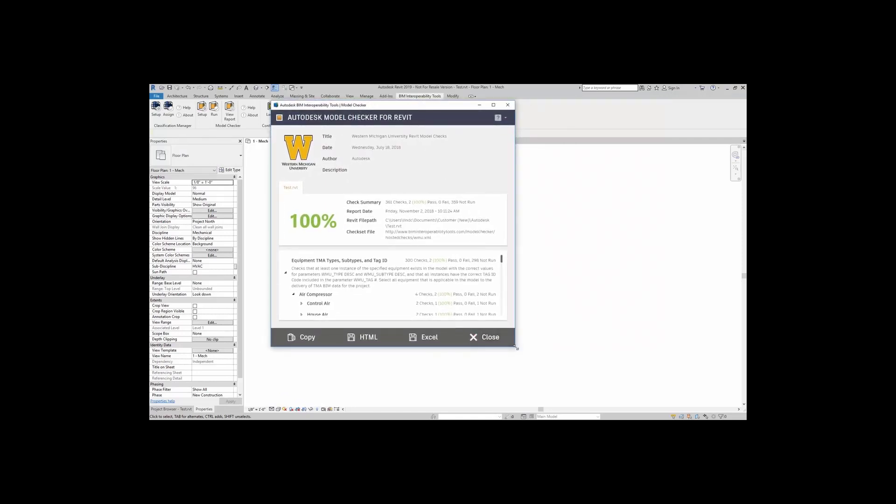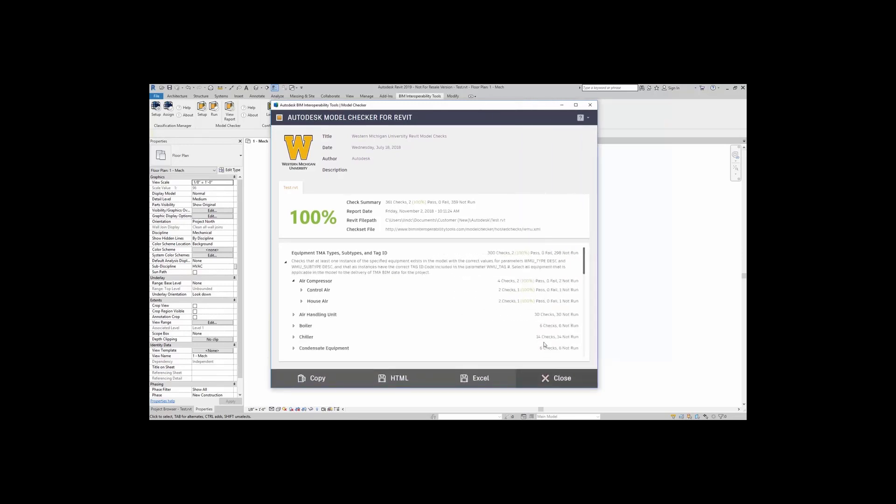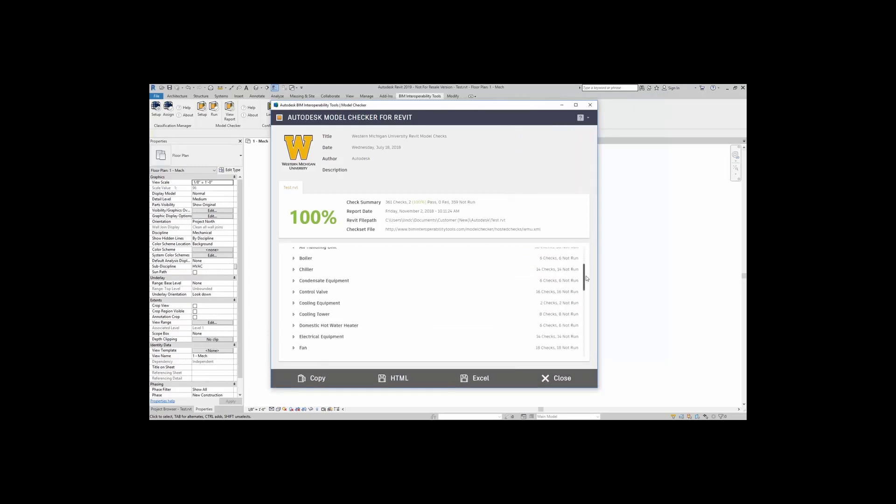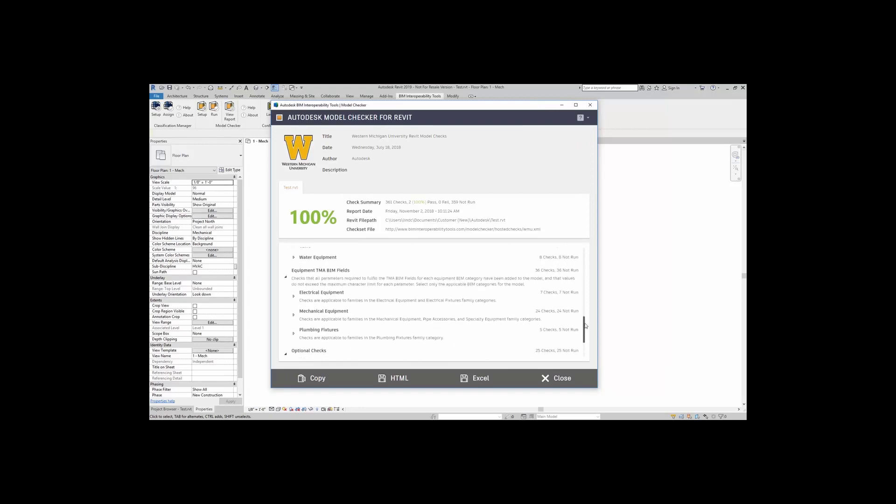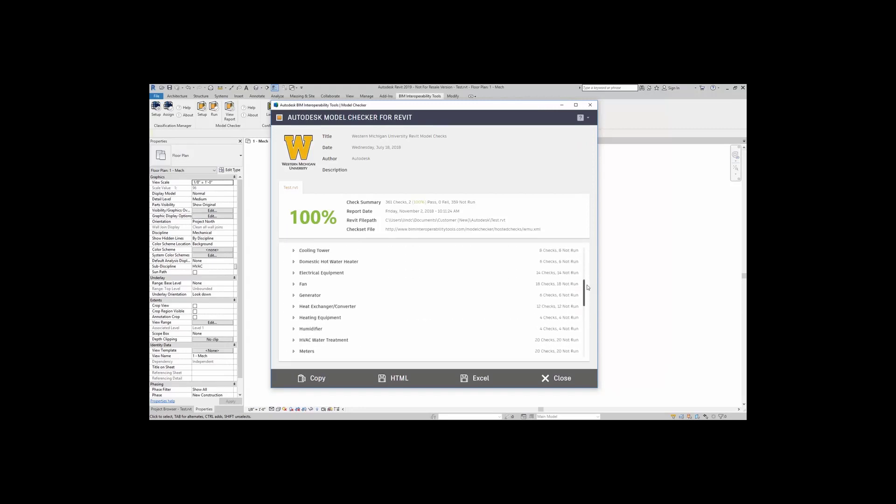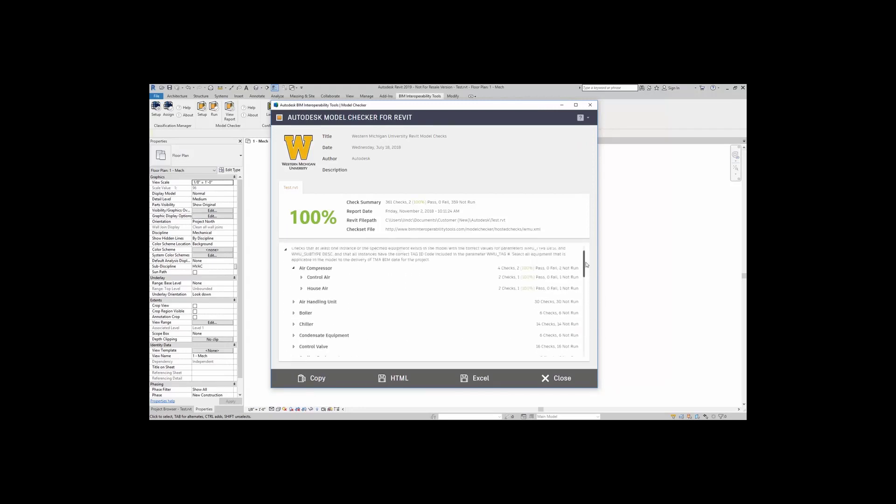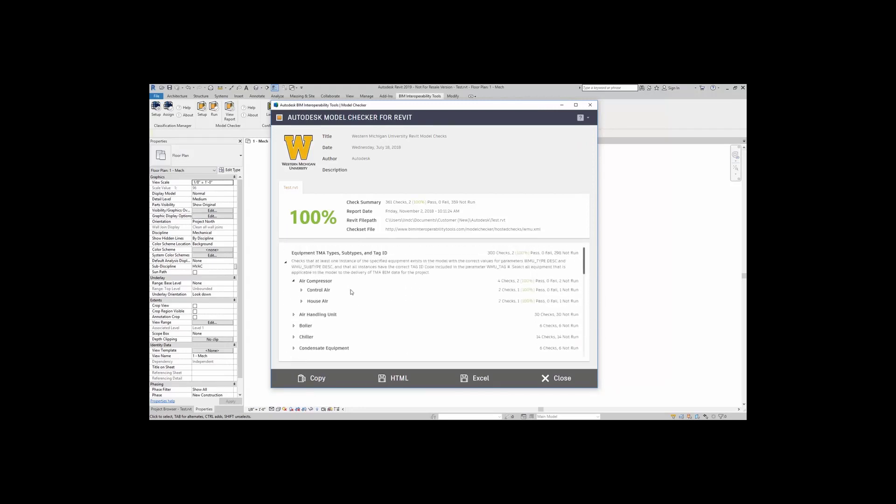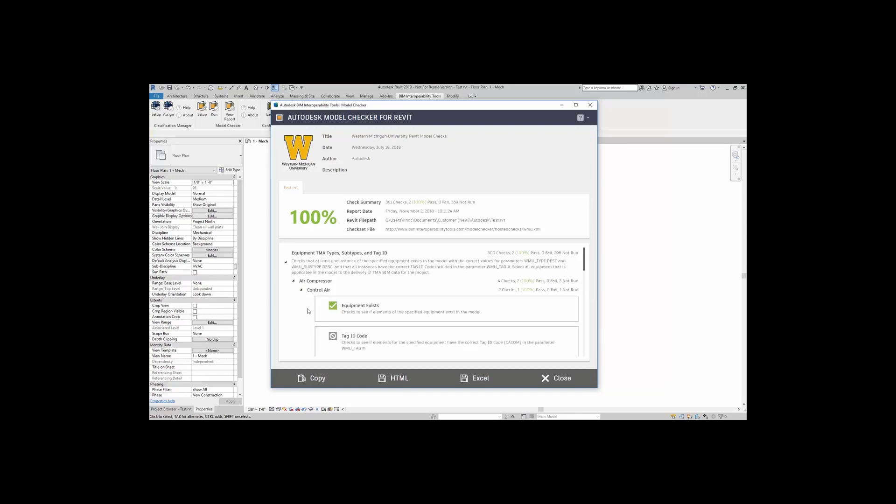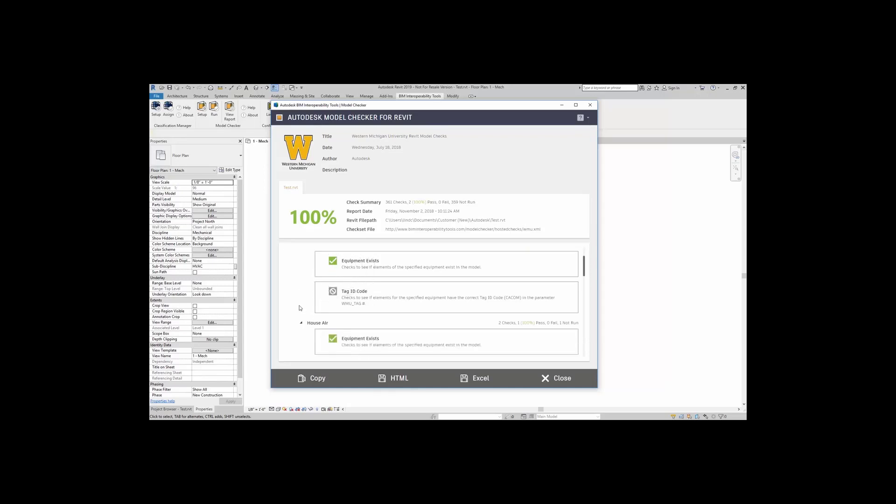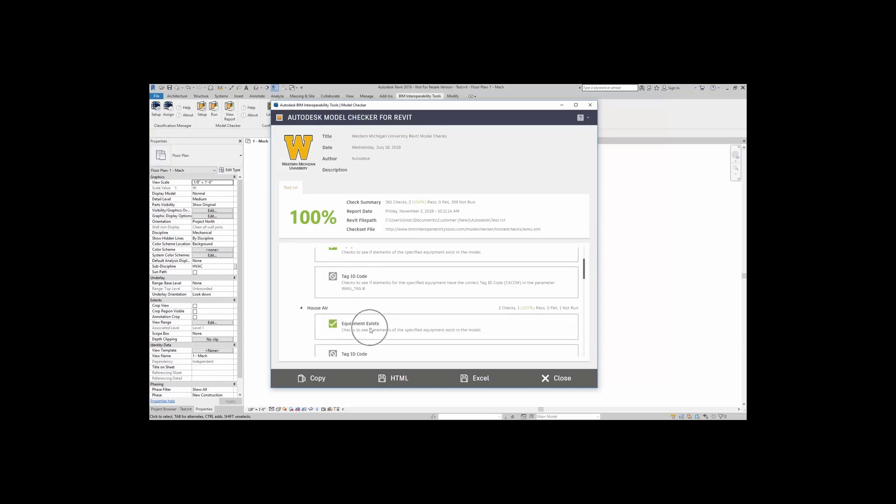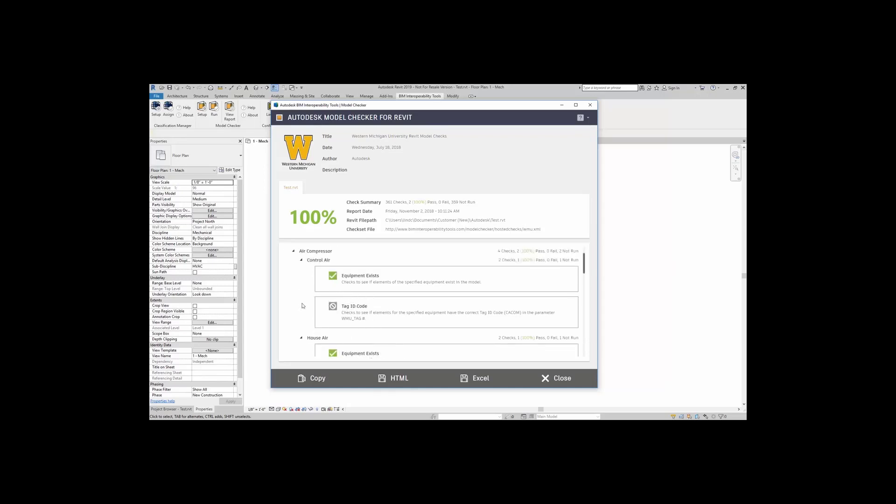Now, of course, when you add in more checks, it's going to take a little bit longer. But here, let's take a look at what's going on. Here it gives me a list of everything that could have been run with this entire check set file. But really what we're looking at is this guy. Air compressor, control air, and house air. It says four checks, two were used, two were passing, zero fail, two were not run. So let's see what's going on. So we can see that the equipment does exist in the model for both control air and house air. That's great. So let's see what happens when one of these fail.